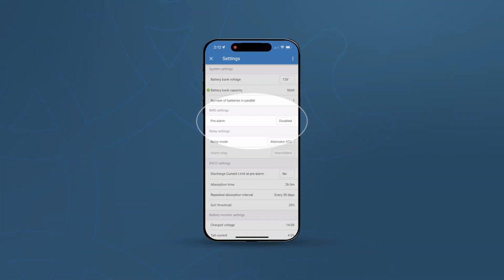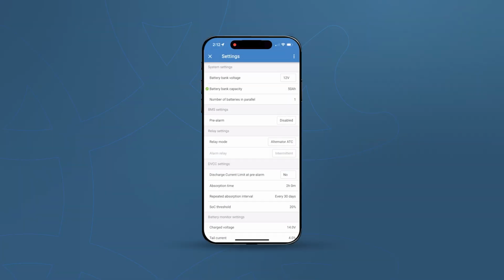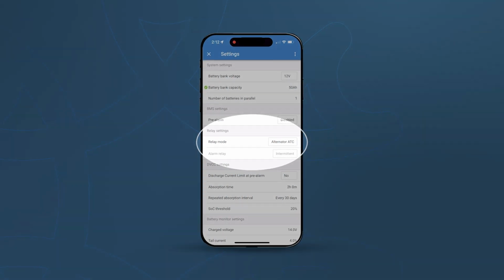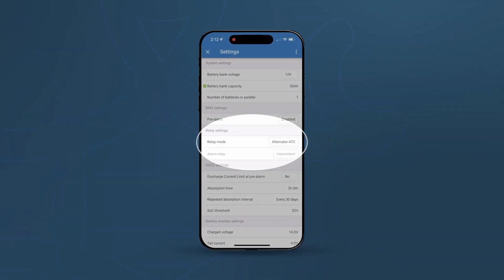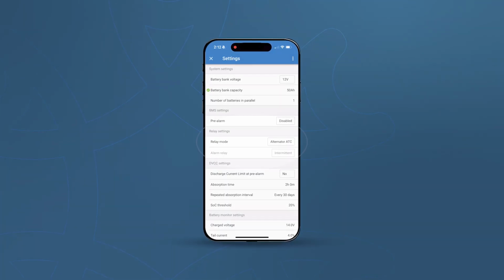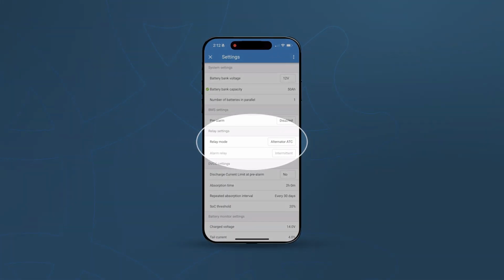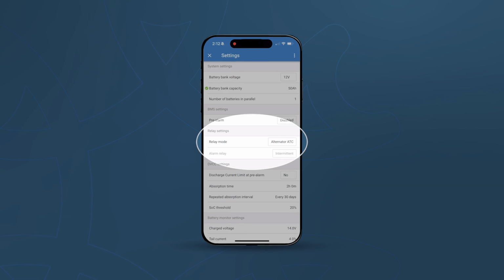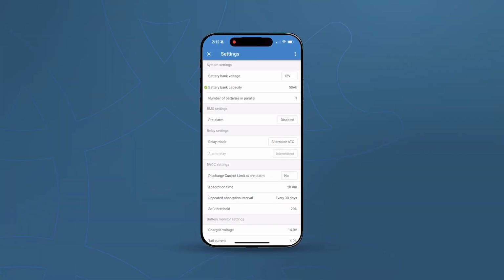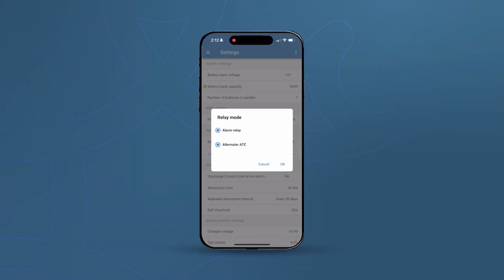Next, we're going to go over the BMS settings, pre-alarm. In our system, we leave this disabled. The next section is relay settings, specifically relay mode. For our system, we're testing Wakespeed units, and hence we're going to set this to alternator ATC. If you had a Wakespeed in here, you would set this to alternator ATC. If you did not have a Wakespeed in here, you would select this to alarm relay.